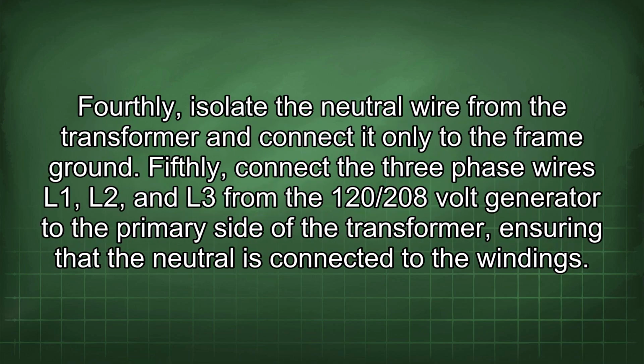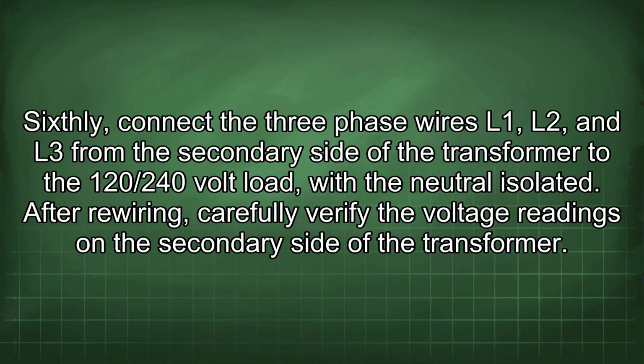Fourthly, isolate the neutral wire from the transformer and connect it only to the frame ground. Fifthly, connect the three-phase wires L1, L2, and L3 from the 120/208 volt generator to the primary side of the transformer, ensuring that the neutral is connected to the windings. Sixthly, connect the three-phase wires L1, L2, and L3 from the secondary side of the transformer to the 120/240 volt load, with the neutral isolated.